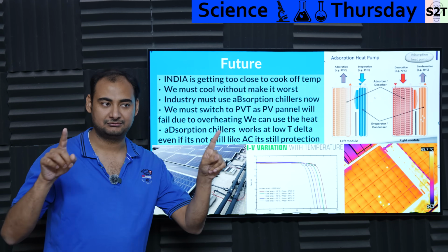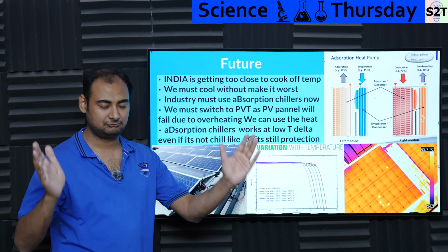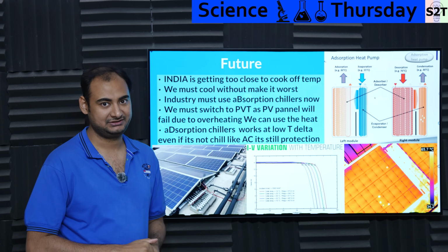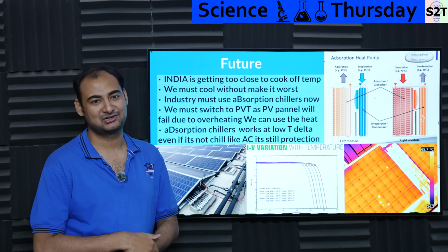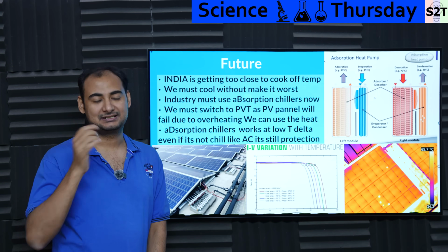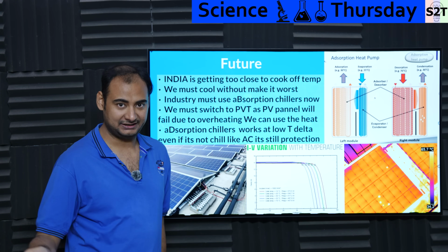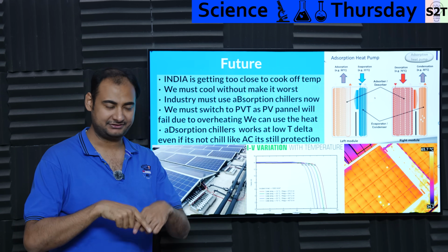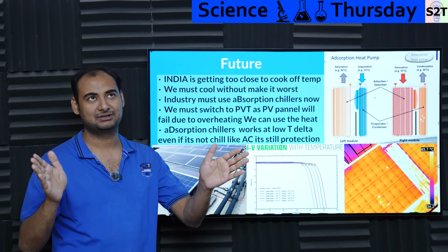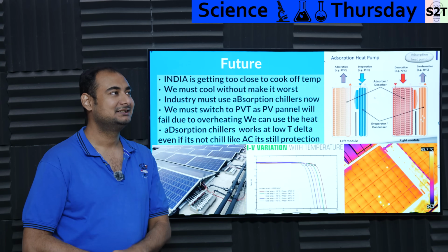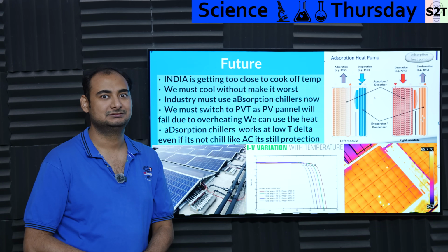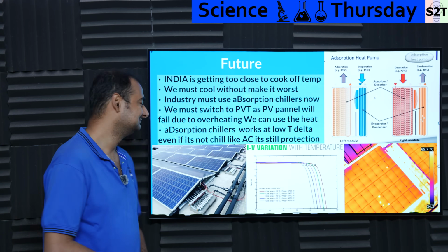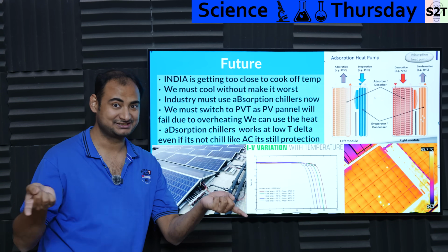For example, if you have a 10 kilowatt solar rooftop, you'll get 20 kilowatt of thermal energy. That's more than enough. That's why I said the COP does not matter. Even if the COP is only, let's just say 0.25, you're good. That's still 10 kilowatt of surface area that gives you 20 kilowatt of heat, and 25% of that is cooling. That's a lot, almost 5 kilowatts continuous. And again, it's not making the situation worse. That's the biggest part.